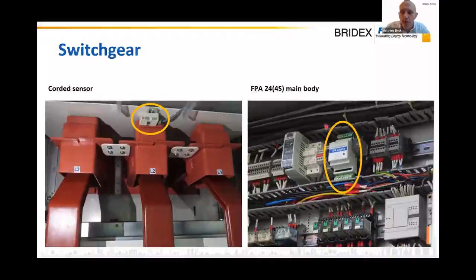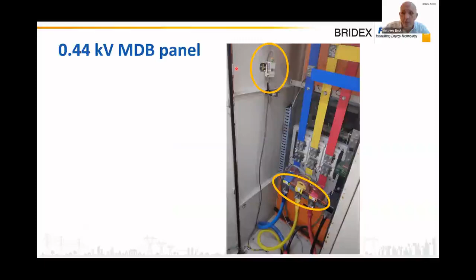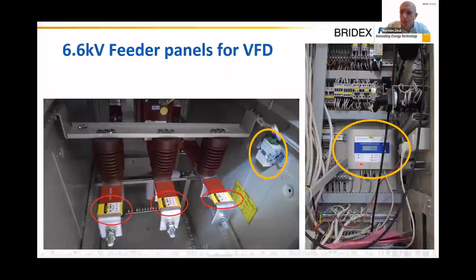Here is an MDB of 400 volts, where the switchgear terminals have been equipped with some stickers, and then on top the sensor for detecting the gas. Here is another medium voltage switchgear of 6.6 kV, where the sensors and the stickers are located close to each other with a concentrator inside the control panel.